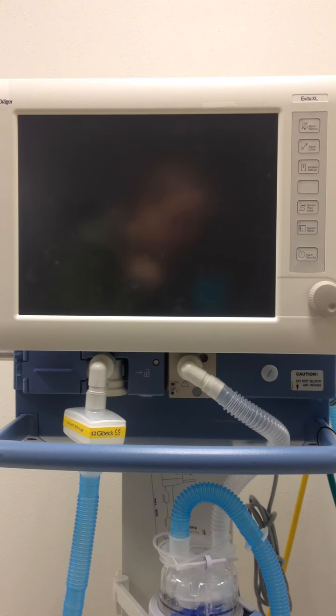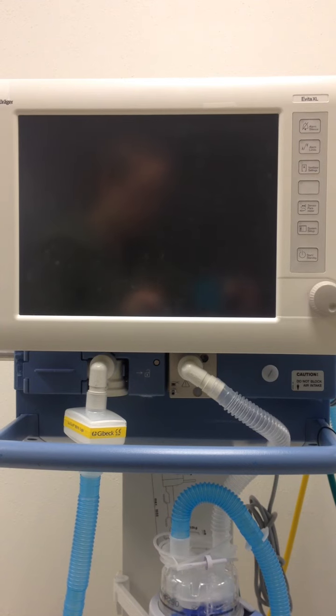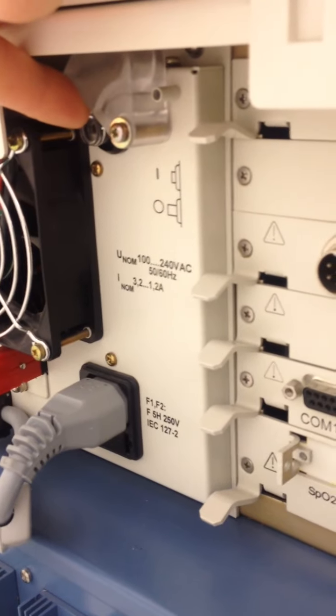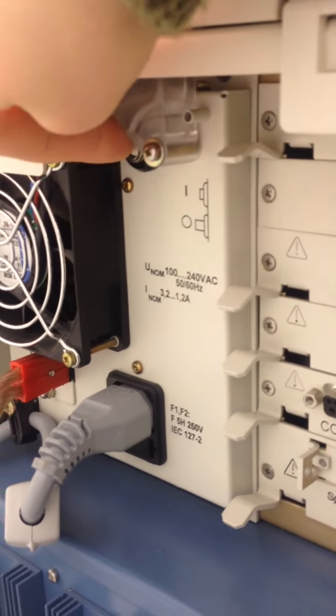Okay, so we're going to go ahead and do a leak test and a device check on the Evita XL. In order to turn the XL on, after you've plugged in your power cords and your gas sources, you can come to the back of the ventilator, and there's a little clear flap. Underneath that, there's a button. You can go ahead and push that, and that will initiate the ventilator.